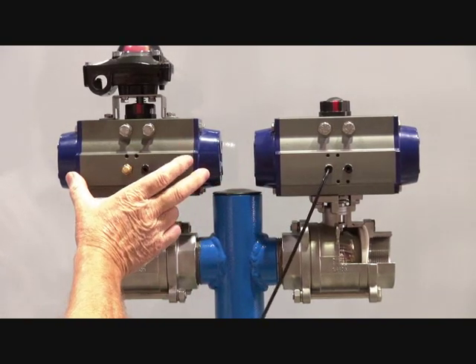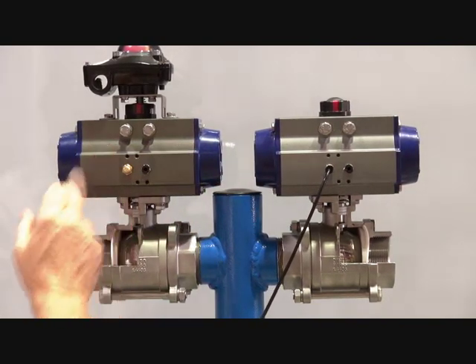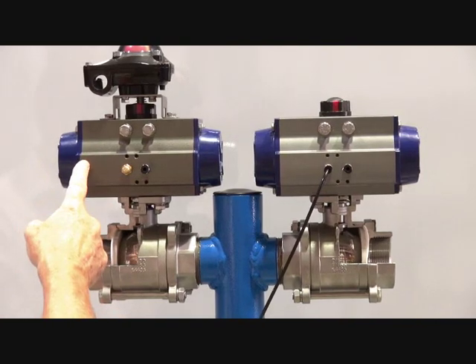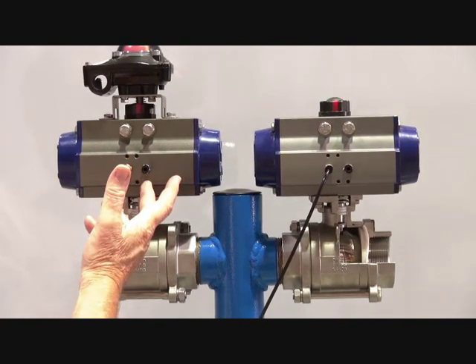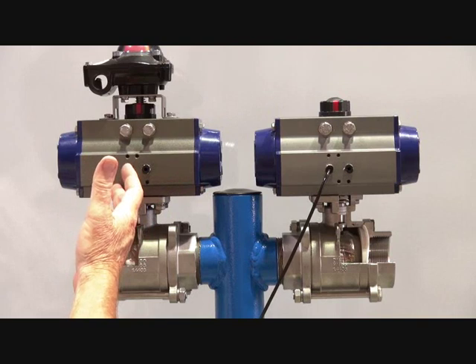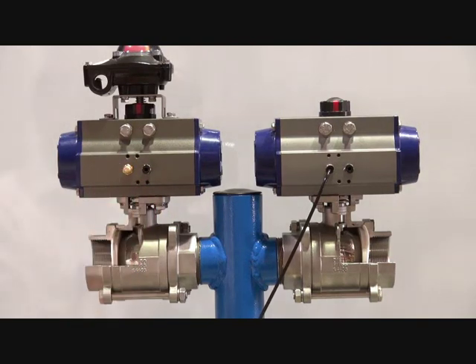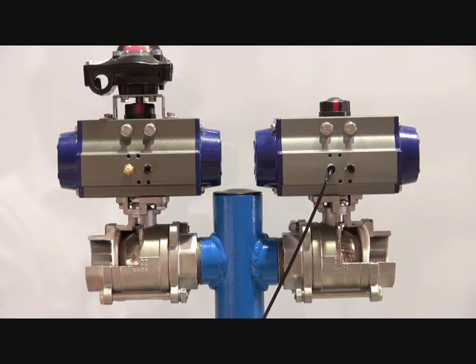Single acting actuator is in fact the double acting actuator with springs. So you can put the air into the spring end as well. It won't affect it. It just assists the spring to close. But the spring is still there to give it the close function or the return function in the case of an air supply or electrical failure.